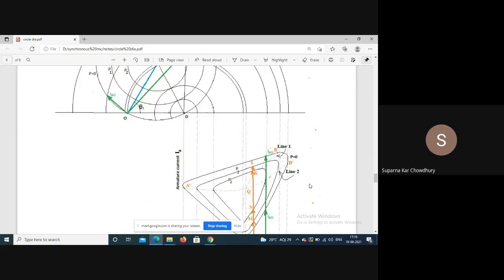In summary, we have two circle diagrams for both synchronous motor and generator. The excitation circle is the locus of armature current for constant excitation, and the power circle is the locus of armature current for constant power. For the synchronous generator, superimposing excitation and power circles gives the operating chart or safe operating zone. For the synchronous motor, the superimposition gives the V-curve. In the next class, we will solve one or two problems on the operating chart.